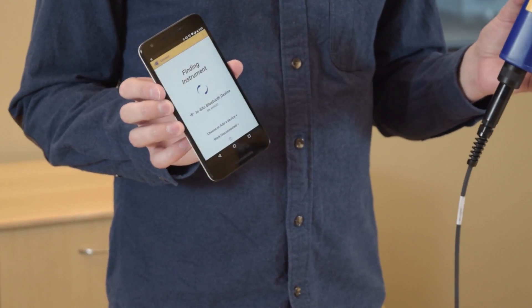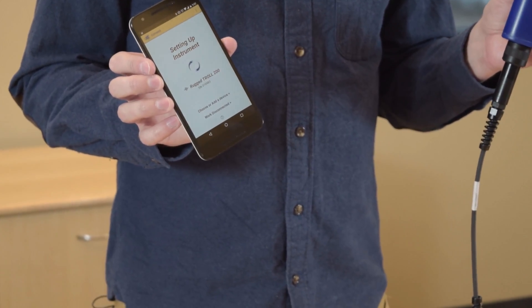You can use VuSitu to set up logs, take live readings, and do any calibrations that you need to do. It works all the way across our full suite of instrumentation — not just the Rugged Troll, but all of our Level Trolls, all of our Aqua Trolls, and every product that you can think of.